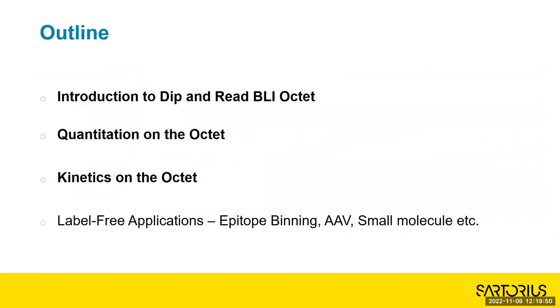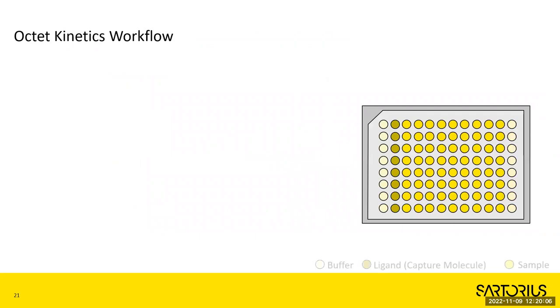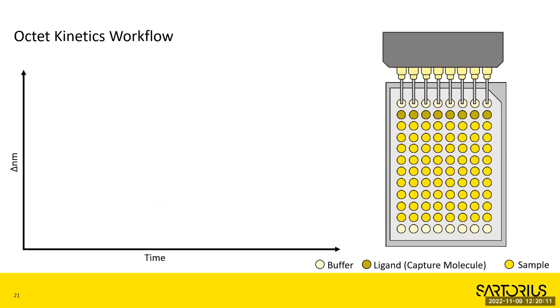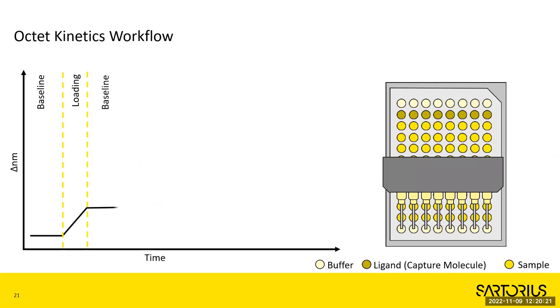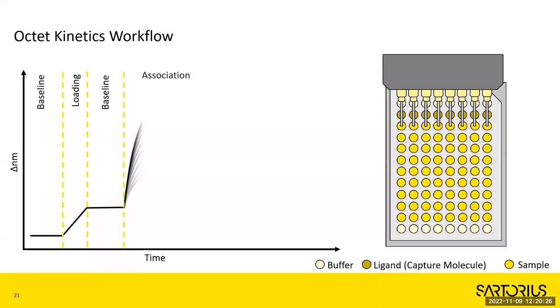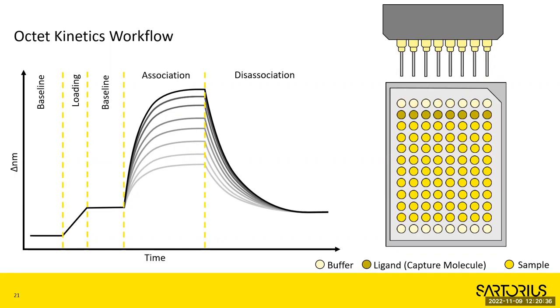Next up is kinetics, which flows right into binding kinetics. In an animated workflow: you have your eight biosensors, you hit a quick baseline to make sure the signal is stable, then go into the ligand loading step. You want to make sure it's stable, so there's another baseline lock step. Then you go into your dilution series of analyte association, then go back into buffer and allow the molecules to dissociate.